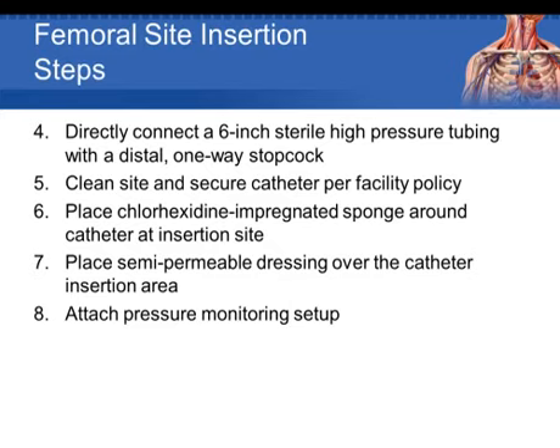Directly connect that 6-inch piece of high-pressure tubing with the one-way distal stopcock, and right now we'll talk about that a little bit. The 6-inch piece of sterile tubing has been intentionally placed in kits and is intentionally being dumped for A-line insertion because it allows us as clinicians to be compliant with CDC recommendations for monitoring setup changes of transducer monitors. So a transducer monitor has to be changed every 4 days or 96 hours, and the distal tubing, this 6-inch piece of tubing with that distal one-way stopcock, allows us as clinicians to change it because, one, it's dumped sterile onto the sterile field, so it's applied to the sterile insertion dressing, and it allows us to change that cycle of pressure transducers without breaking the insertion site itself, without having to go all the way down to the hub.